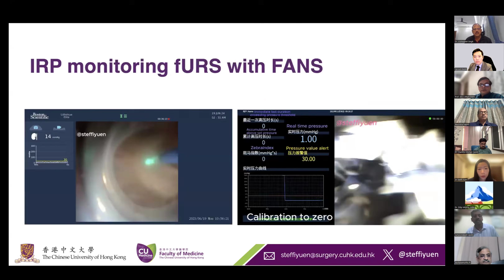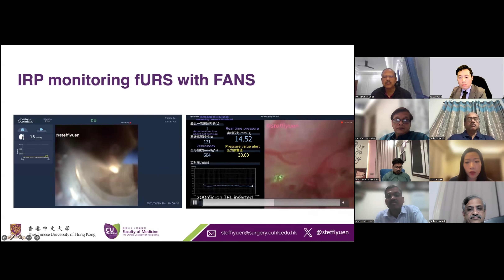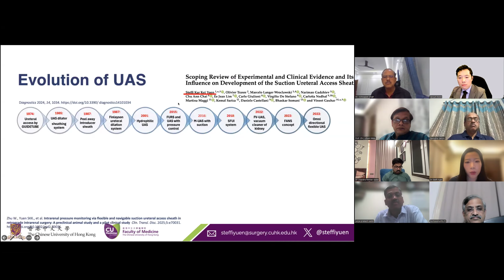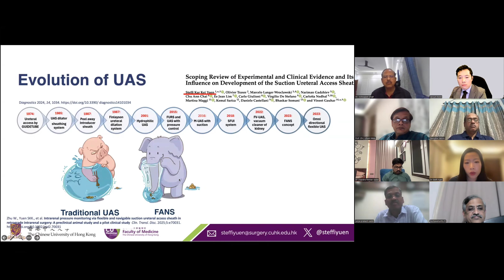So these are videos of how it looks. In essence, it will show a real-time pressure on the screen the whole time, and it will have an alert or flashing red signs if it's above the set limit of 30 millimeters mercury. So we've moved from conventional sheaths to suction sheaths to intrarenal pressure monitoring FANS. There are different brands and different configurations. I will not go into details, but you can look at the publications.